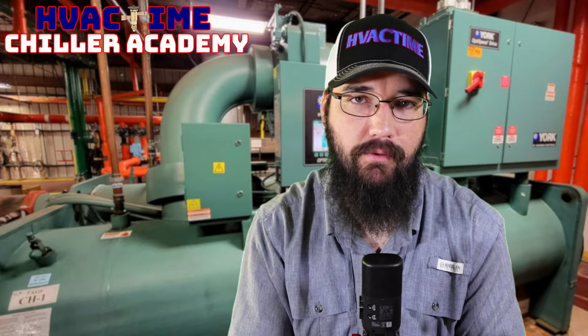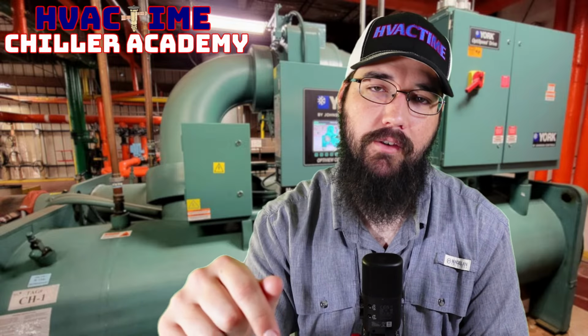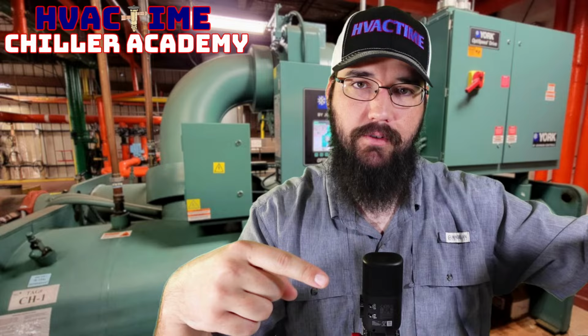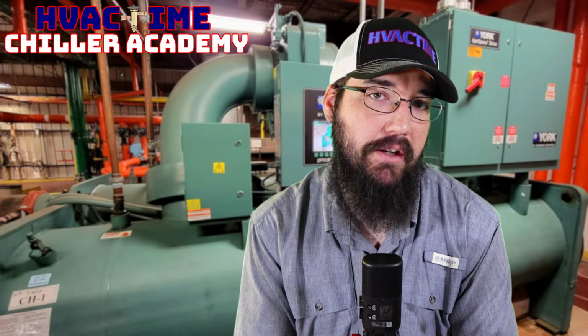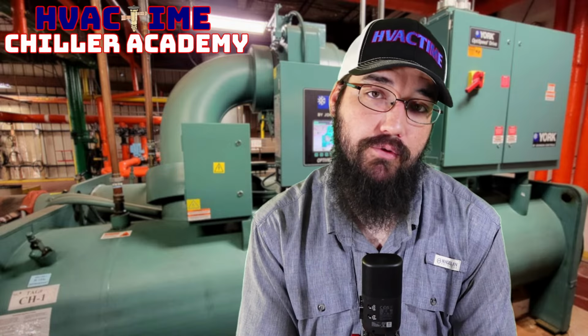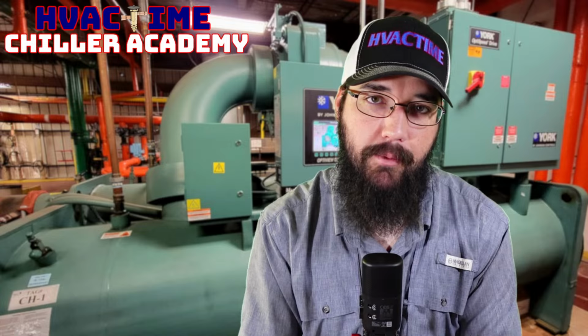And so they came off of this extended plenum, which wasn't even necessary for the way this house is designed. But they put this extended plenum in, and then turn around and ran this 6-inch run to these 2 6-inch drops, but used a T on the first drop of the run and then let it just feed to the second. Now the problem is, the way they built this plenum, they come in and then go immediately straight out the other side with another primary drop for the kitchen. So what actually happens there, majority of the air to that entire side of the house, which has very poor airflow at the moment, just shoots straight through into the kitchen, and basically the dining and the add-on get next to no air at all. And that's because they're coming off on the side of the plenum, while the kitchen is coming off on the end, right in alignment with the inlet, the feed duct coming in.